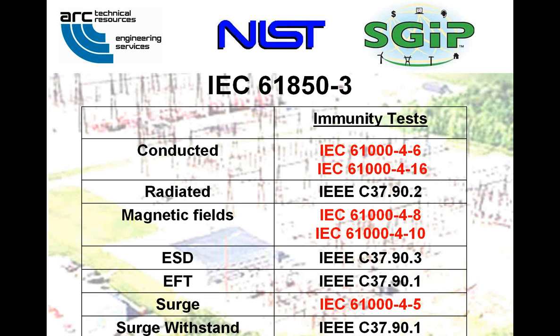IEC 61850-3 invoked the test levels for substation products that were copied into the draft and called out for products used in Zone A, which was inside the substation fence. That's shown in the middle column here. Zone B is defined in IEEE 1613.1 as outside the substation fence out in the distribution network. That requires a lower test level in each case, taken from 61000-6-5, which was in our white paper. So the highest level is inside the substation fence and 1 level lower everywhere else out in distribution.